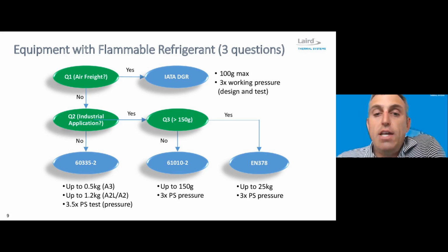That's if it's less than that. If it's greater than that, then it's the EN 378. And so these also have their limitations as to how much the charge can be, but all of them generally, you can see here, are driving towards a pressure test or pressure rating of 3 times typical operating. So a lot of this expertise has been pushed down into the manufacturers, where we need to come up with these safe operating systems that can work with these refrigerants that normally haven't been safe over the years.